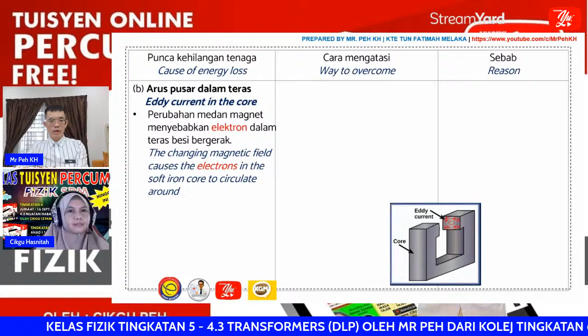So how does this happen? The changing magnetic field causes the electrons in the soft iron core to circulate around. The flow of electrons is actually the current. So the changing magnetic field causes the electrons to circulate around and produce the eddy current in the core. The eddy current will be lost as heat, same as the resistance of the coil - it will also be lost as heat.